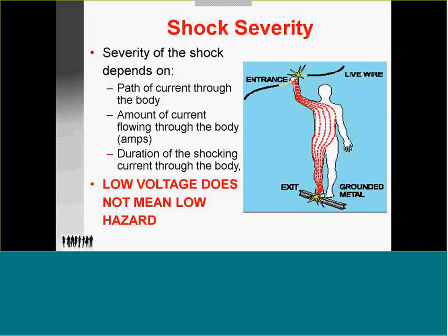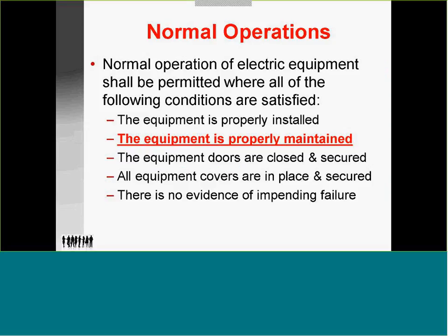In an amperage circuit, there's damage, but I've seen pilot circuits that are 30 to 35 volts running at 40 to 50 amps, which is a killer. It is permissible to work live below 50 volts as long as the amperage is low. So operation by code is in conditions. The unit is properly installed. It means installed to the manufacturer spec and to the code.